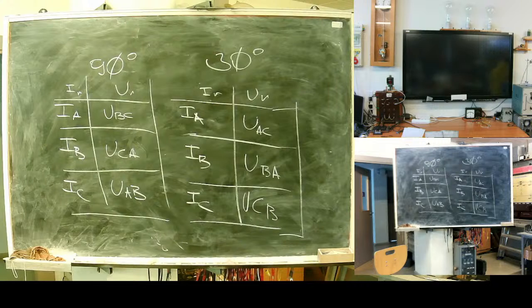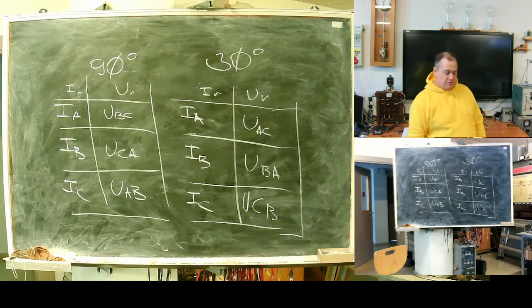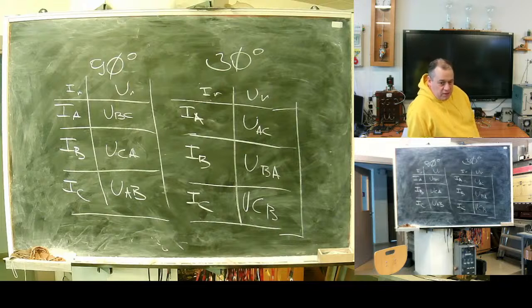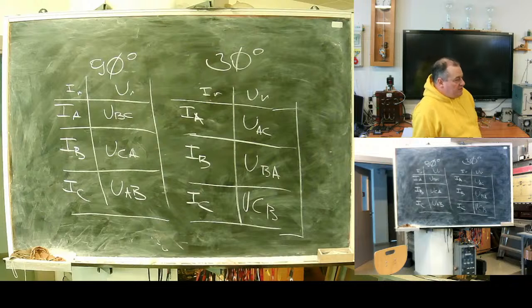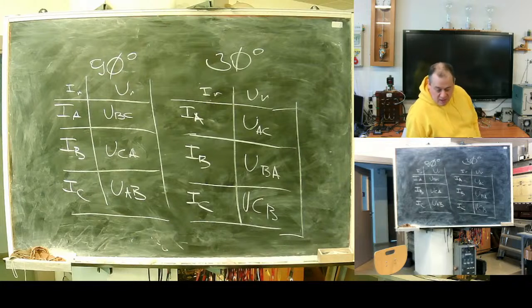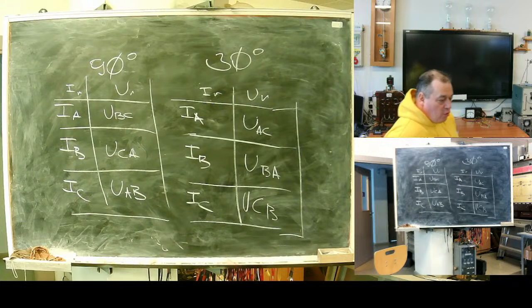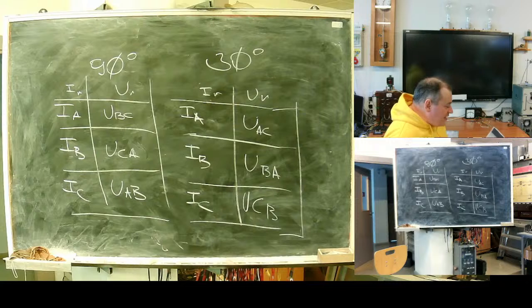In older times, remember the idea of installing two current transformers in A and C to save space and money. Old protection panels also had two relays, not three, not a full set. In case you have a set of two relays, 90 degrees is reliable. With the 30 degrees schematic there will always be a fault case where it's not reliable, because safely operates only the relay on the leading phase. The lagging phase may not operate.